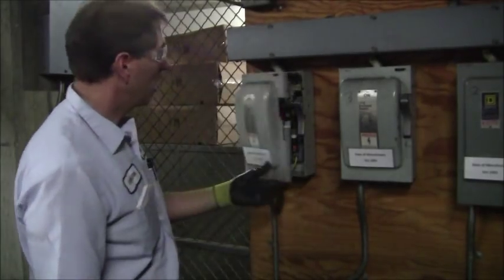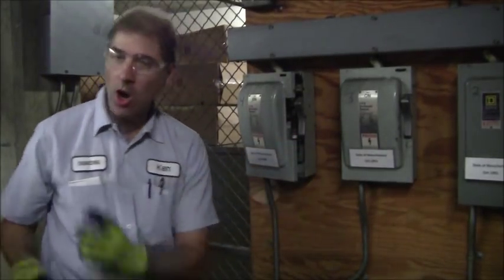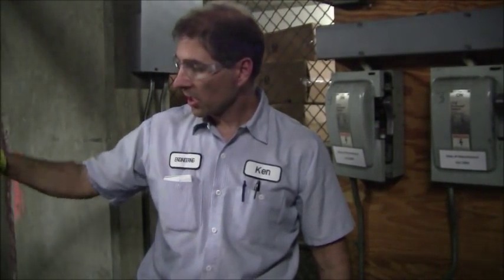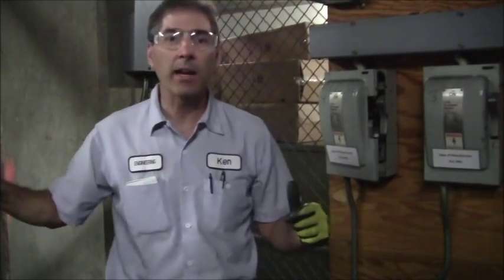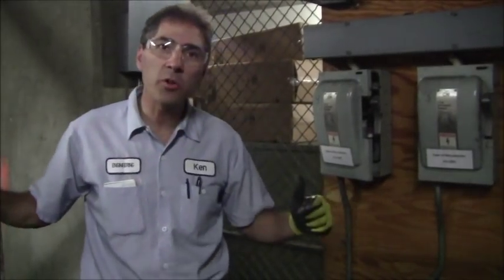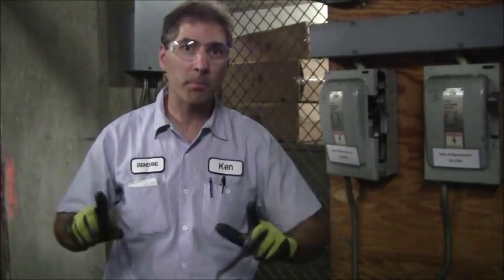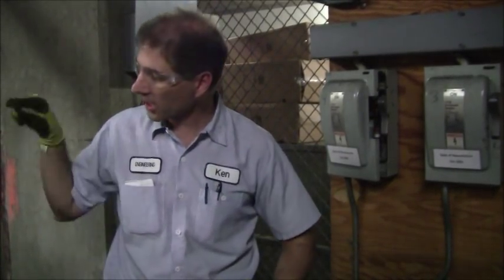Now, if I turn that on, I know that I'm going to be producing 3 full phases of electricity to my contactor. My contactor is already pulled in. We already saw that it was pulled in. The question is, why did that fuse blow? At this point in time, I don't know why the fuse has blown. So the next thing I want to do is just do an electrical check on my compressor. We're going to do that right now.